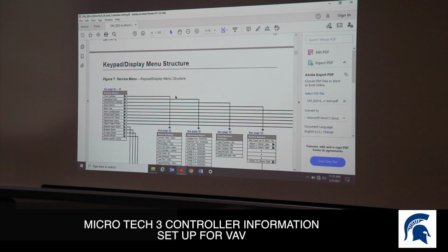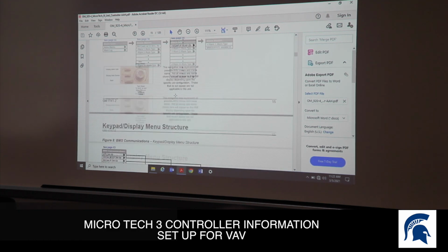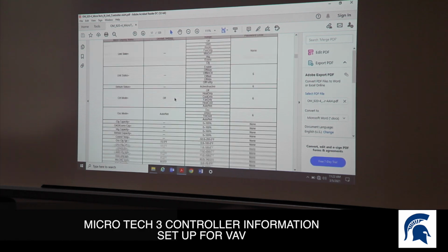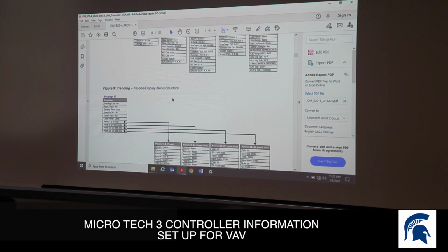Those are all the configuration set points in this controller, so you can understand why it's best not to mess with them. It should be documented how they set it up. Did you have a commissioning agent on the job? Yes, I'm sure they verified everything is set up exactly the way it's supposed to be. You should never have to go that far down. The problem here is it's such a sophisticated control that if you change this, it would affect three other things over here that need to be changed so everything aligns. So you just don't want to, okay?